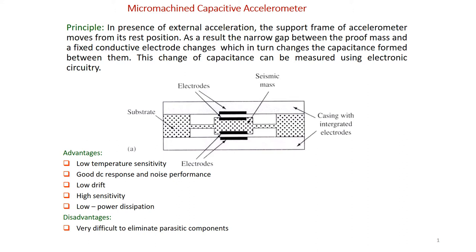The main accelerometer will be put inside the frame. The basic principle remains the same — when the whole system is installed on a platform subjected to vibration or acceleration, the frame will move and the inside mass-spring-damper system will also move, producing some relative displacement. In the previous case, that relative displacement or stress was converted into resistance and then into voltage — that was the basic principle of the piezoresistive type. In the capacitive case, that displacement change is converted into capacitance change, which is further converted to voltage with the help of circuits, giving the measurement of the unknown acceleration.